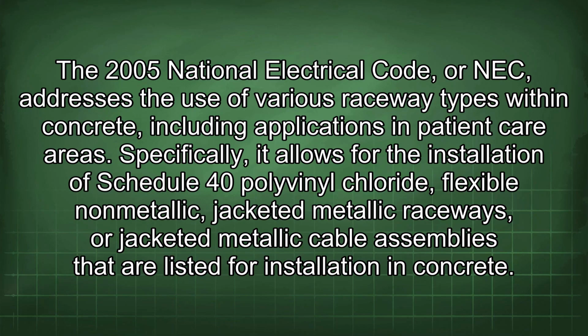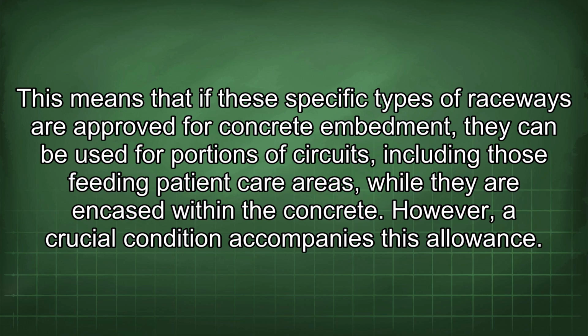The 2005 National Electrical Code, or NEC, addresses the use of various raceway types within concrete, including applications in patient care areas. Specifically, it allows for the installation of Schedule 40 polyvinyl chloride, flexible non-metallic, jacketed metallic raceways, or jacketed metallic cable assemblies that are listed for installation in concrete. This means that if these specific types of raceways are approved for concrete embedment, they can be used for portions of circuits, including those feeding patient care areas, while they are encased within the concrete.